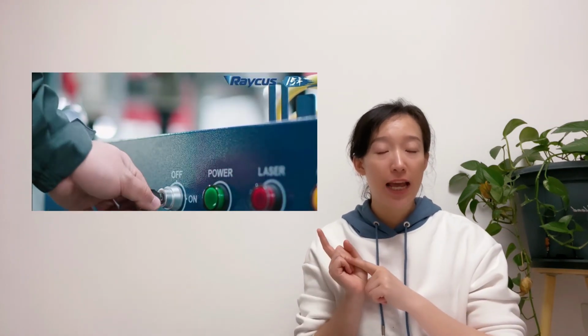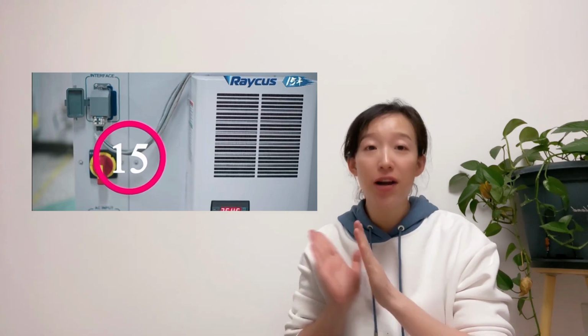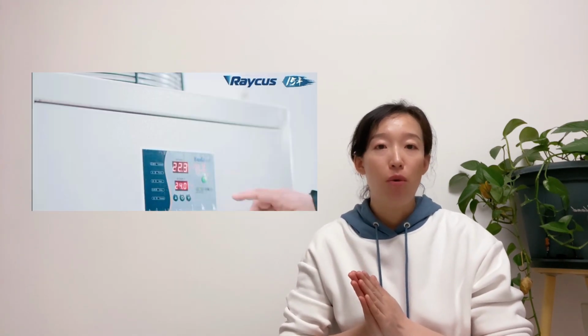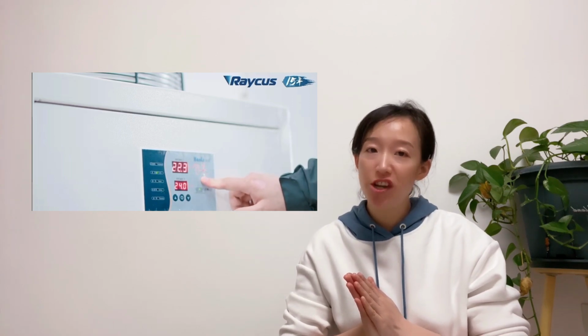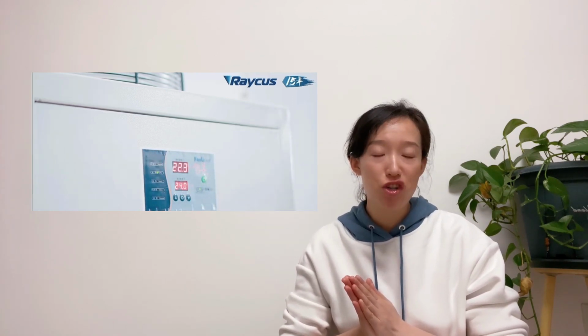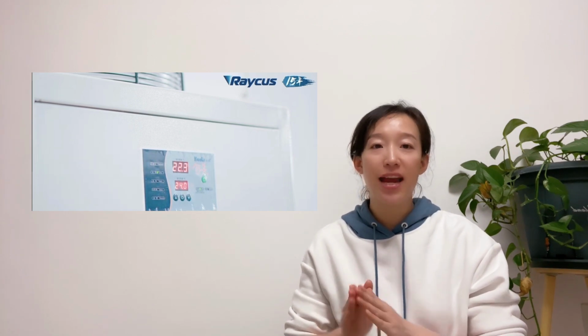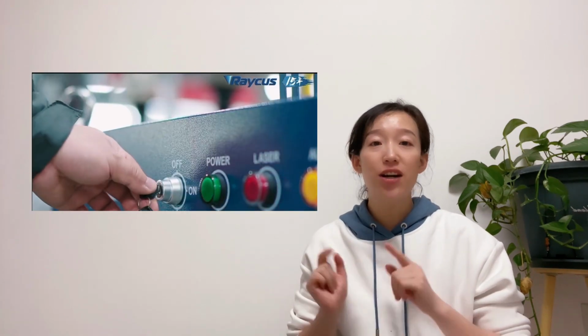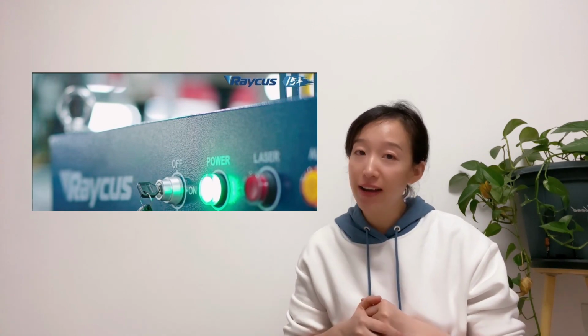First, equip the lasers with a separate air conditioner. Second, when starting the laser, first turn the key switch of the laser to off. Turn on the power of the laser and let the air conditioner run for about 15 minutes before turning on the chiller. When the temperature of the water chiller reaches the set temperature, turn on the laser by turning the laser key switch to the REM.